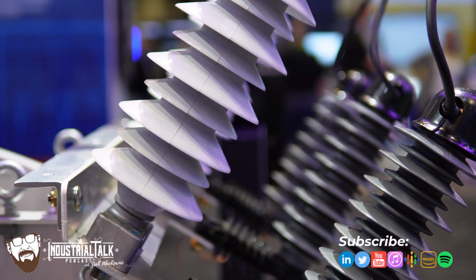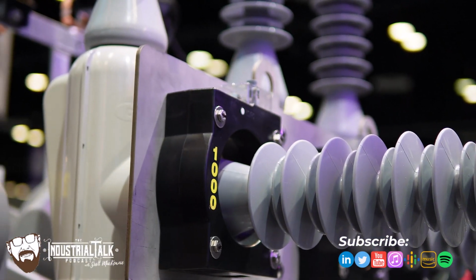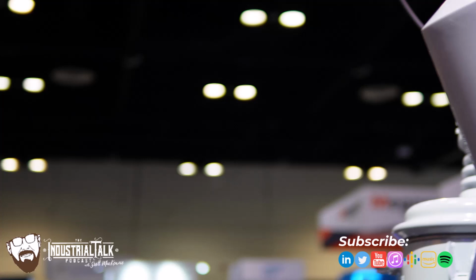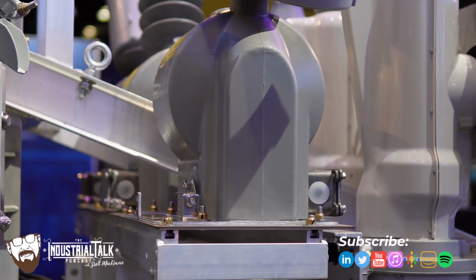It's so true. And one of the things that they do is that they generate a lot of harmonics, which can cause damage to equipment and other bad things. And so we have developed a sensor that has very high resolution on magnitude, but it also gives you that picture of what the harmonic situation is at that point of the grid. And we have all this wired completely integrated into the control cabinet, and we are not only using this recloser as a protection device, as a metering point, but it's also a power quality node. That is just all in one device. Brilliant. Now that's thinking outside the box. I like that. Absolutely. I like that.